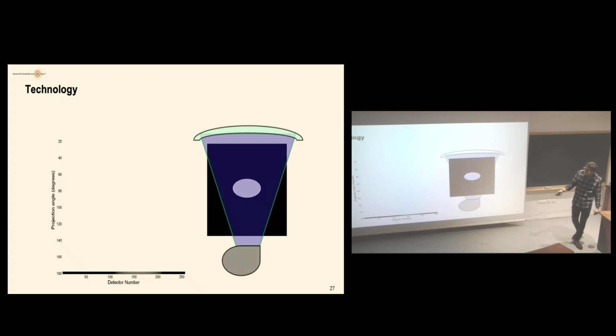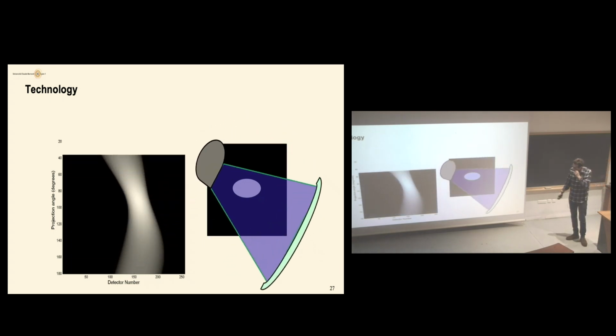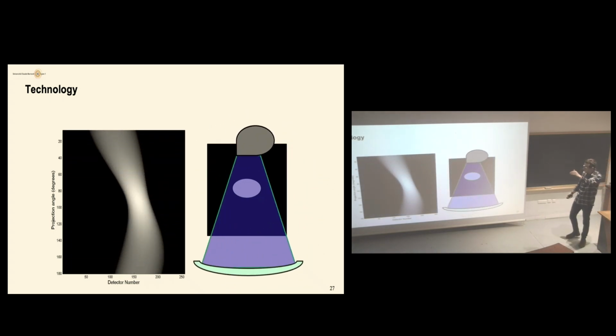That means that if you put a patient at the isocenter and an X-ray tube here with a zooming factor around 1.3, you will end up with a spatial resolution that won't go lower than 600 to 700 micron. This is an important limitation, especially for coronary arteries, because they are really small, sometimes 2 millimeters. That means that in 2 millimeters you will have a very low number of pixels. So for this task and many others, you need to increase the spatial resolution.